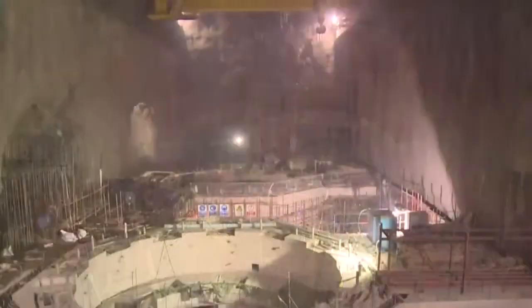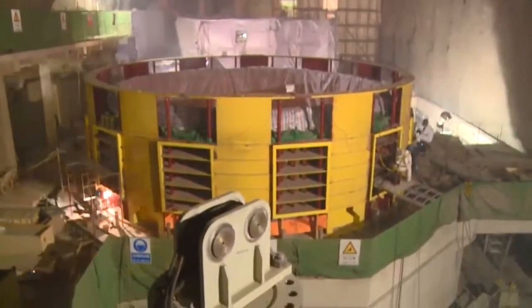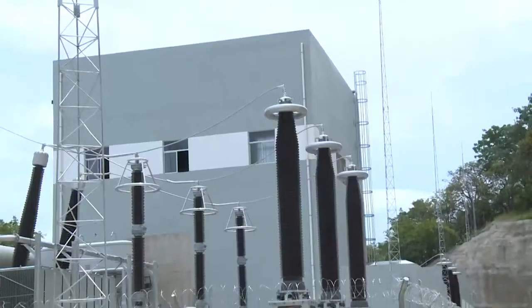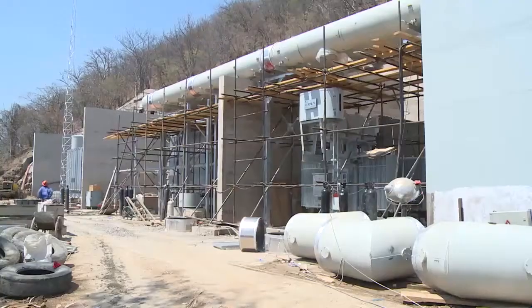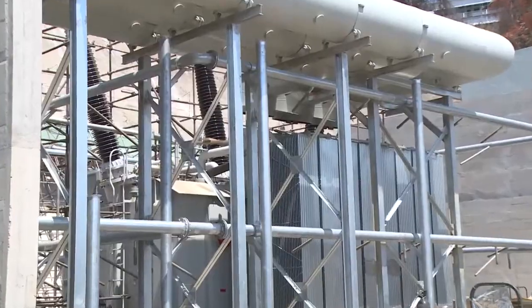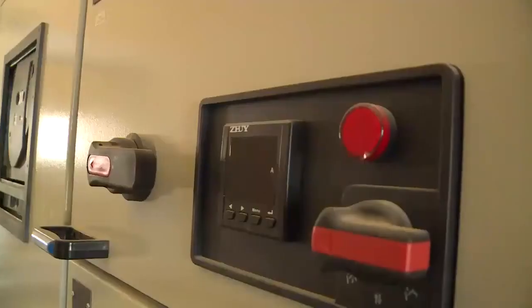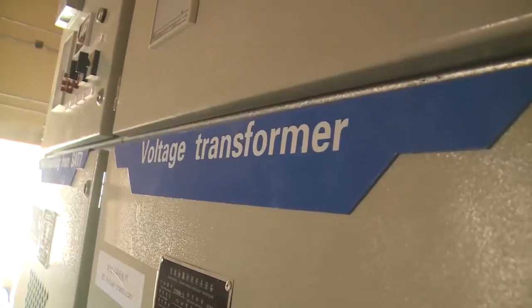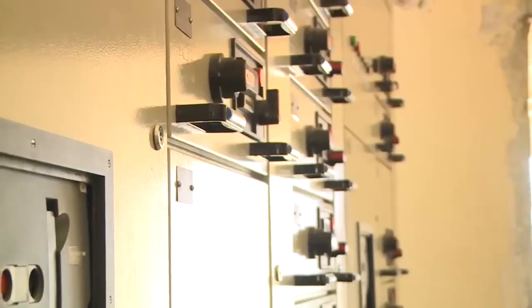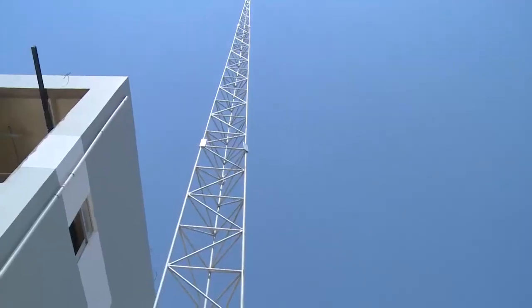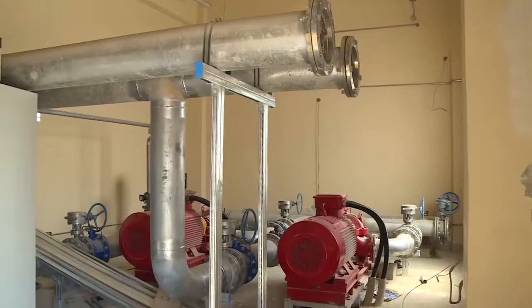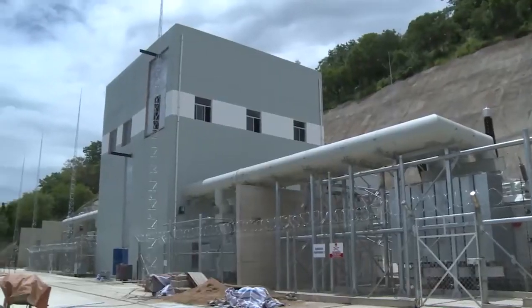The new plant generates a total of 15.75 kilovolts. This alternating current is then transmitted to the transformer platform. Here, a series of transformers step up the generated electricity to 330 kilovolts. The transformer platform is where the step-up transformers, accessories, ventilation and cooling equipment for the powerhouse are installed.